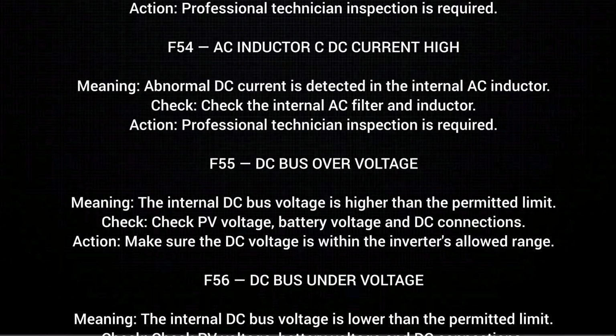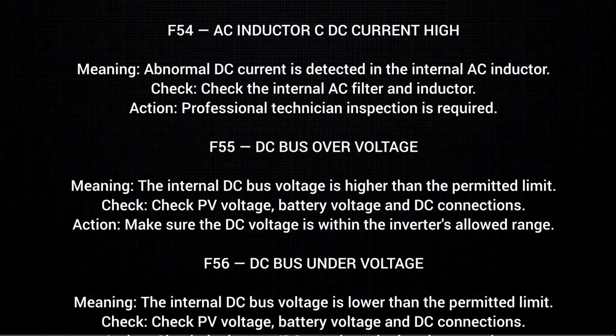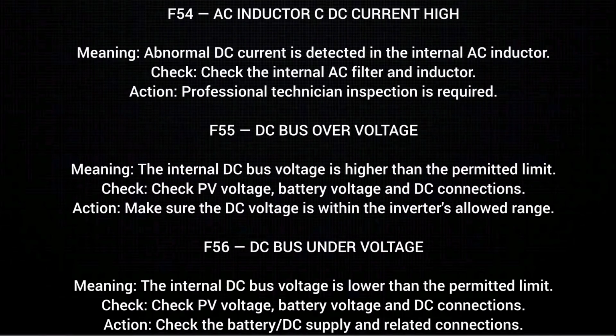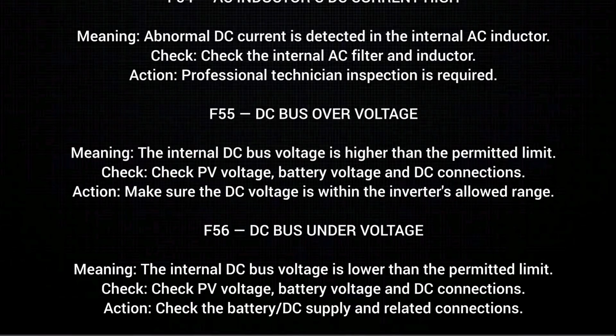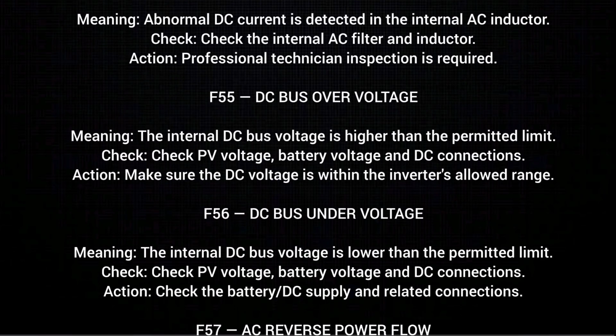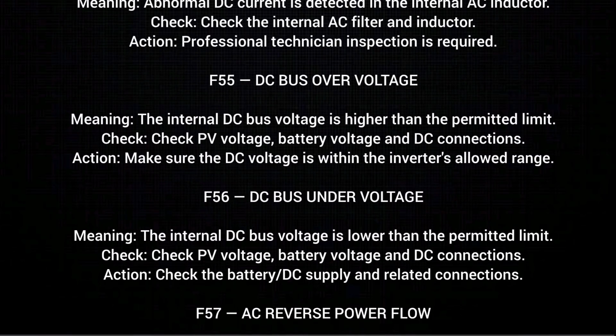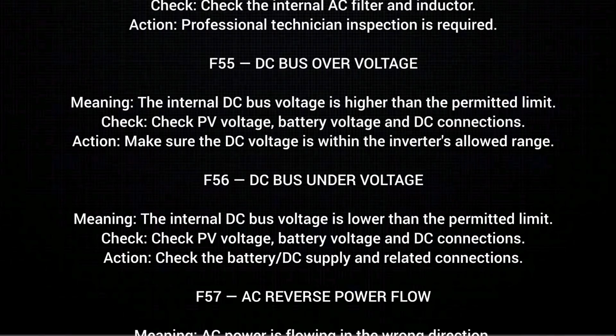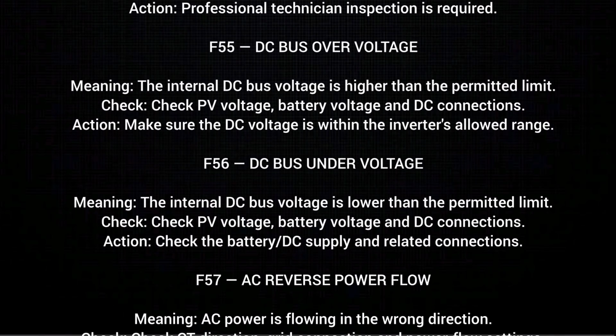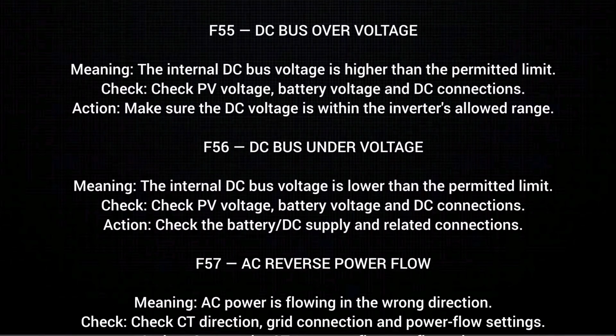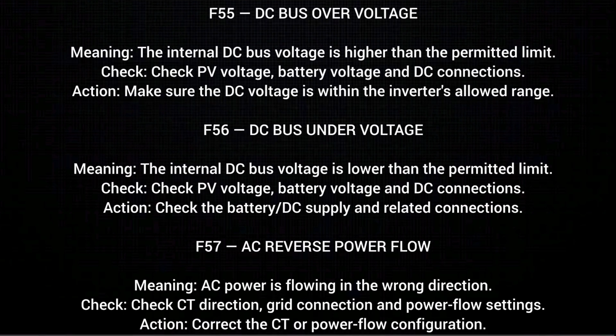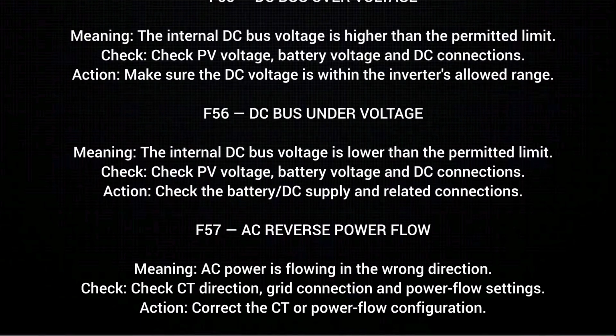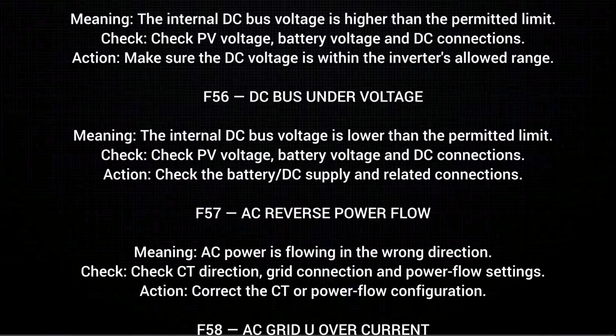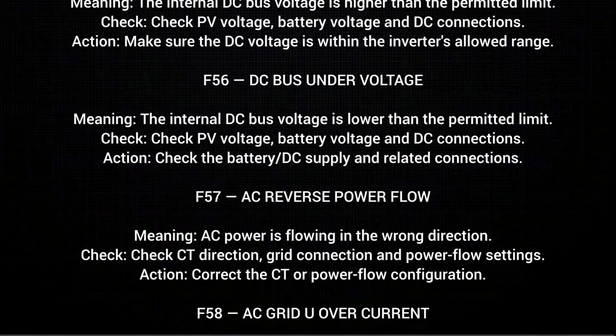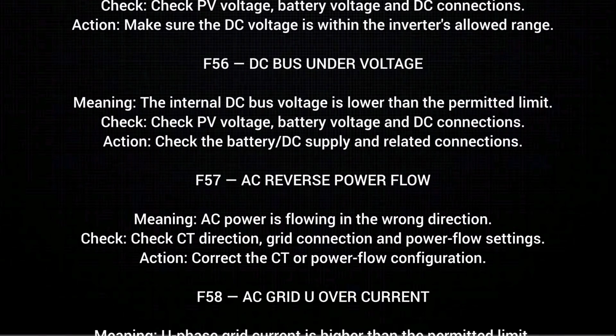Action. Make sure the DC voltage is within the inverter's allowed range. F56. DC bus under voltage, meaning the internal DC bus voltage is lower than the permitted limit. Check. Check PV voltage, battery voltage and DC connections. Action. Check the battery DC supply and related connections. F57. AC reverse power flow, meaning AC power is flowing in the wrong direction. Check. Check CT direction, grid connection and power flow setting. Action. Correct the CT or power flow configuration.